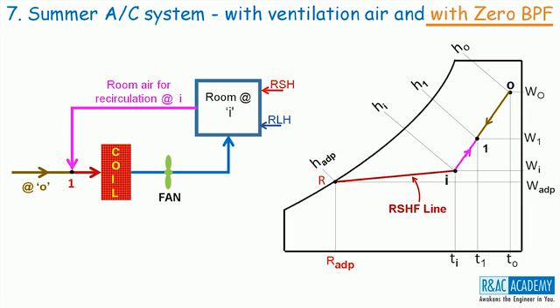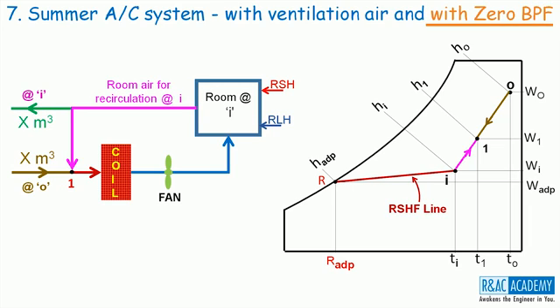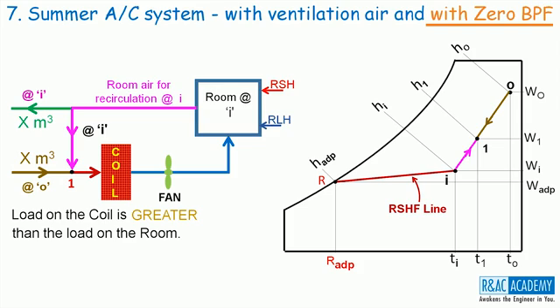Let us now plot this process of mixing of air streams on the psychrometric chart. T1, W1 and H1 are the properties corresponding to state point 1. If we are taking x cubic meters of ventilation air into the system, then we must throw x cubic meters of recirculation air out into the atmosphere. The remaining recirculation air at state I will be used in the system. Please note here that the coil is handling the ventilation load in addition to the room loads. Therefore, the load on the coil is greater than the load on the room.